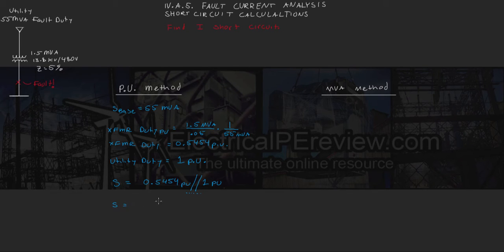So S is going to equal 1 over 1 over 0.5454 plus the reciprocal of 1 per unit, which is also 1. We can solve this as 0.3529 per unit. If we want to find the actual value of that, we're going to multiply by our base that we selected as 55 MVA.